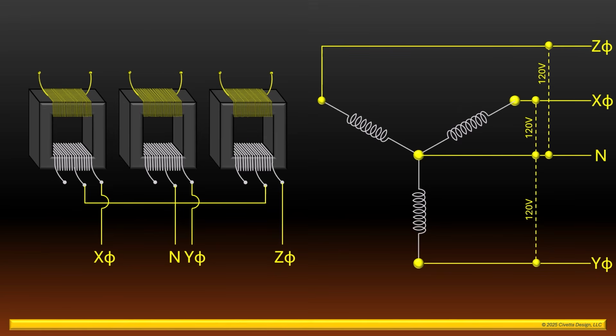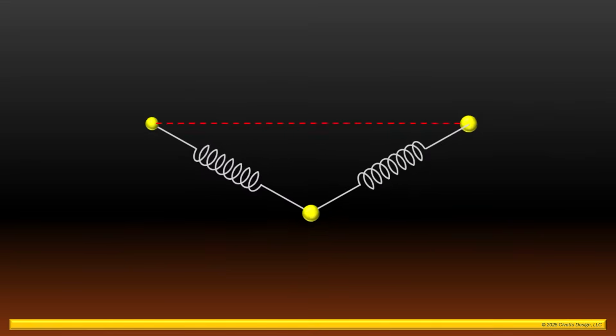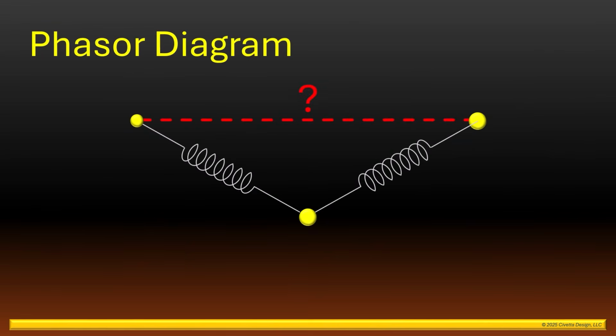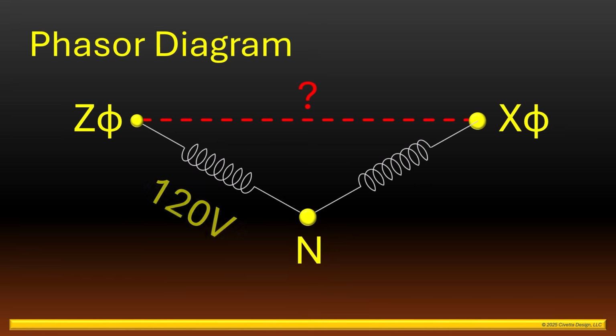To determine the phase-to-phase voltage potential, say between Z phase and the X phase, we'll need to look at the phasor diagram. To determine the voltage potential between the Z phase and the X phase, we just need to use some simple geometry again. We know the phase to neutral potential is 120 volts. We also know this lower interior angle is 120 degrees.